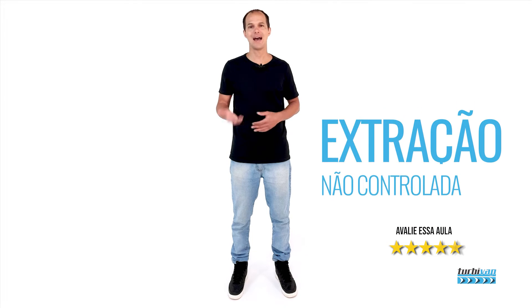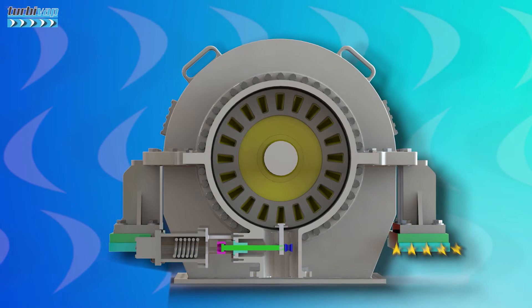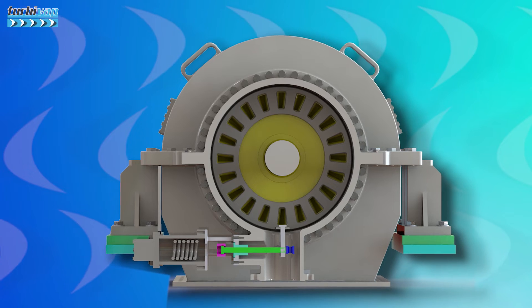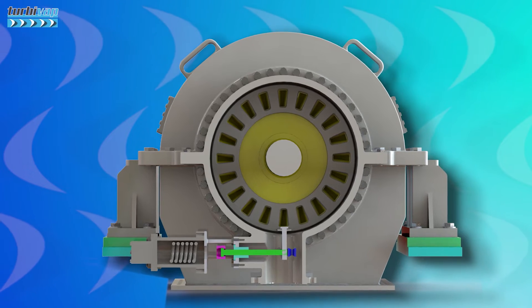Also, uncontrolled extractions, known as takes or bleedings: in this type of extraction, it is simply a removal of steam from inside the turbine, and its pressure depends on the current turbine load. This type of extraction is used for turbines in regenerative cycles.